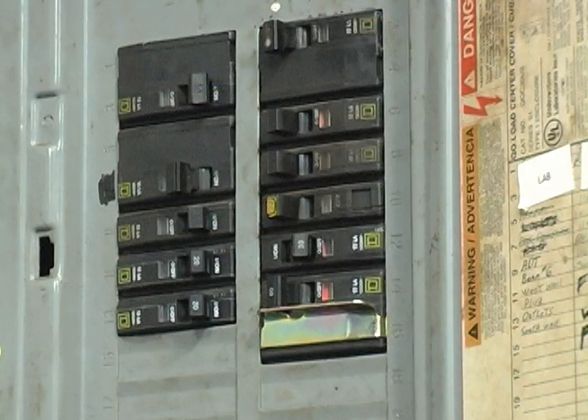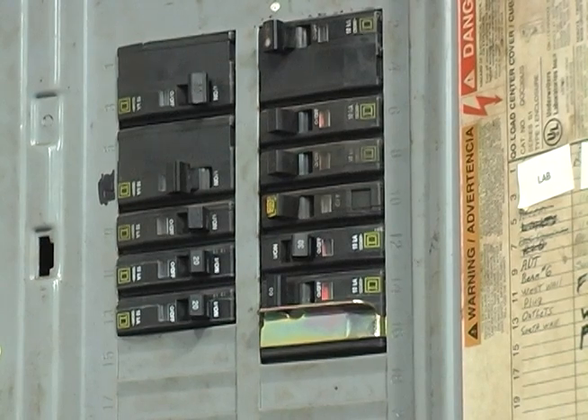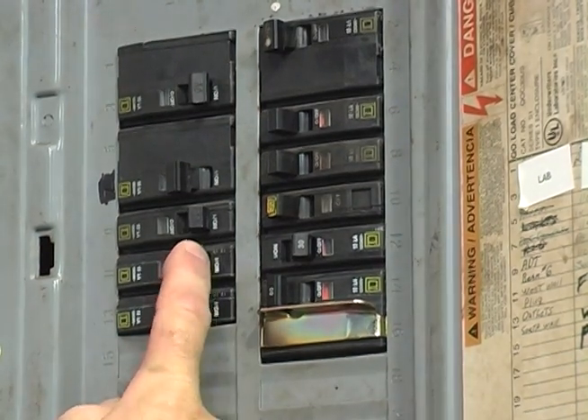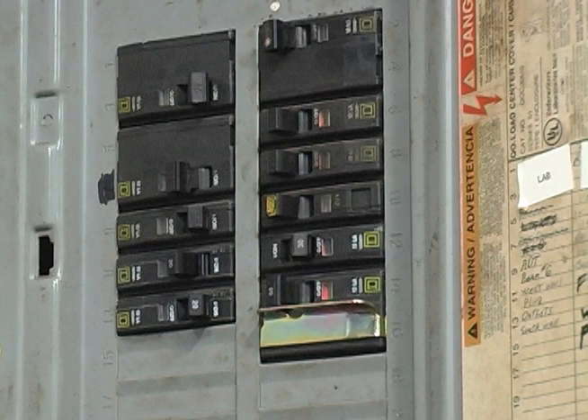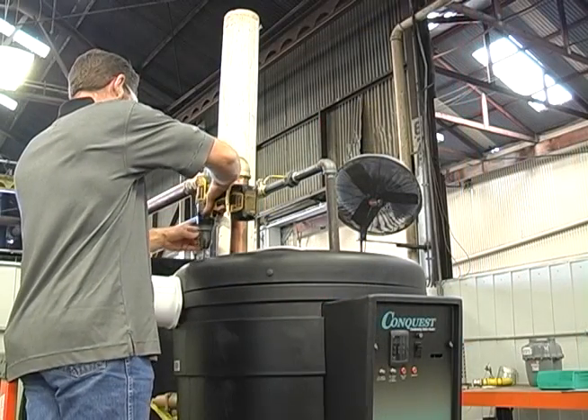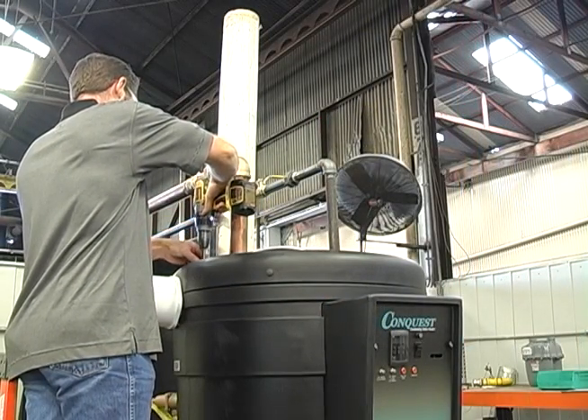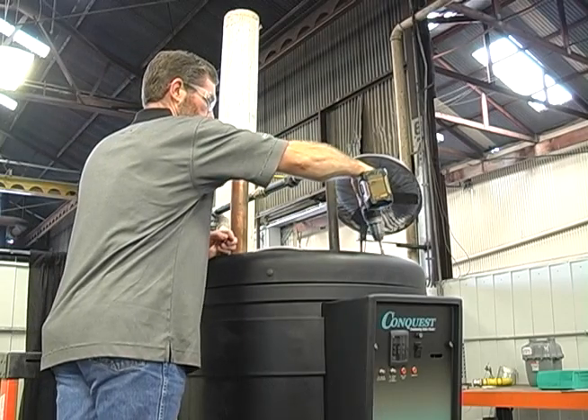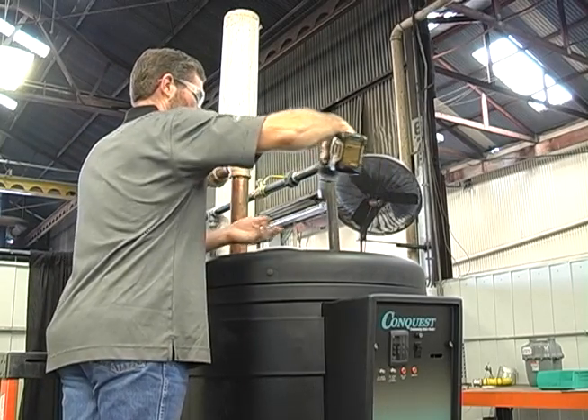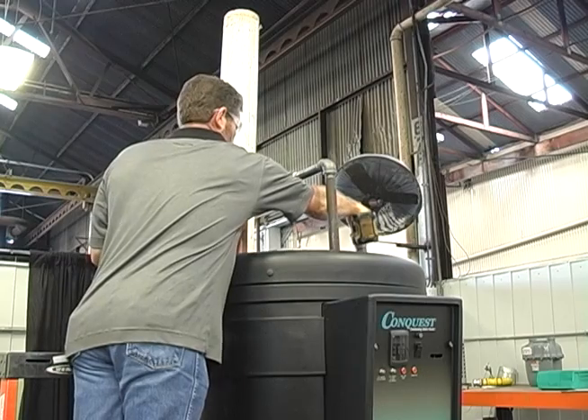The first step in the startup and commissioning process is to locate the electrical service panel for the equipment and to identify the circuit breaker dedicated to the water heater. The circuit breaker must be in the off position. Do not provide electrical power to the water heater until you have verified leak-free service at the water and gas connections. In order to gain access to the gas train components, the top pan of the water heater will have to be removed. It is held in place with screws that are removed from the top of the heater.